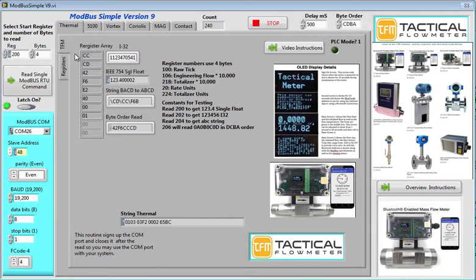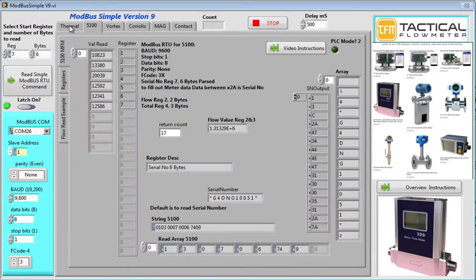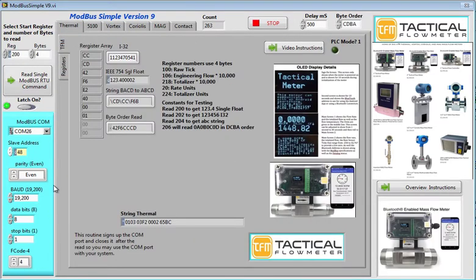As we switch the tabs up here, the variables down here in blue, defining the ModBus COM, slave address, which may be different for your meter, give you something to start with. With the thermal mass flow meter, we have some constants to enable you to read a single float. If you read command or register 200, 4 bytes, you should get 1, 2, 3, 4 as a single float.